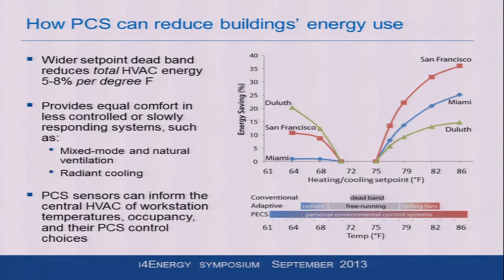Okay, this is the benefit for this type of thing, and it's remarkably large. If you can widen the temperature set point from the conventional 72 to 75 that you find in U.S. buildings, though I must say now they're actually often just a single unitary point, you tend to save somewhere on the order of 5 to 8% of your total HVAC energy for each degree that you can either increase or decrease the set point. That's a huge amount. So you can see totals here that are running up to 40%, especially in this area.